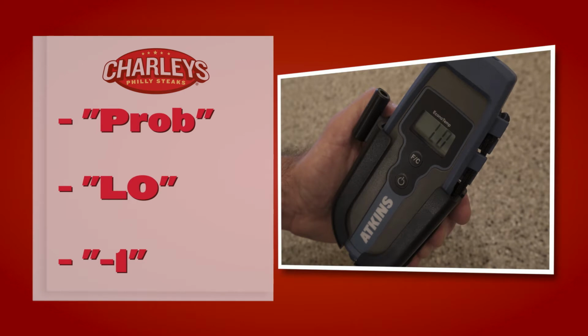If the temperature does not reach 32 degrees after a few minutes, you will need to contact the manufacturer to recalibrate or purchase a new Atkins thermometer. If the thermometer reads prob, low, or -1, check that the probe is plugged in. If the probe is plugged in and the thermometer has prob, low, or -1, your probe most likely needs to be replaced. If the battery icon, the letter B, or BAT appears on the display, change the battery.